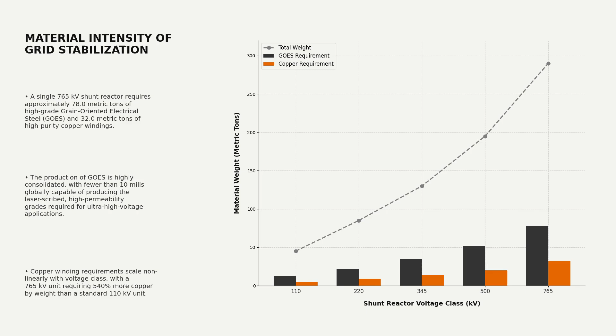Copper requirements also scale nonlinearly with voltage. A 765 kilovolt unit requires 540% more copper by weight than a standard 110 kilovolt unit. This high material footprint exposes grid infrastructure directly to base metal supply chain volatility.